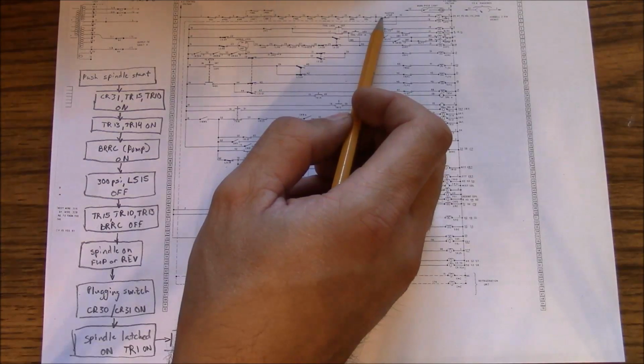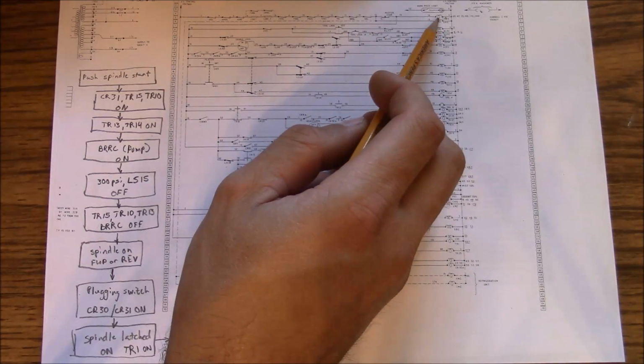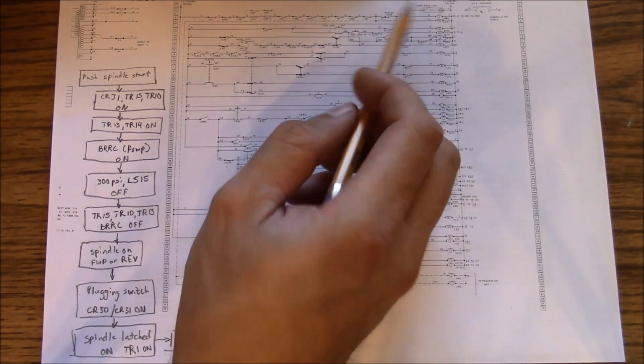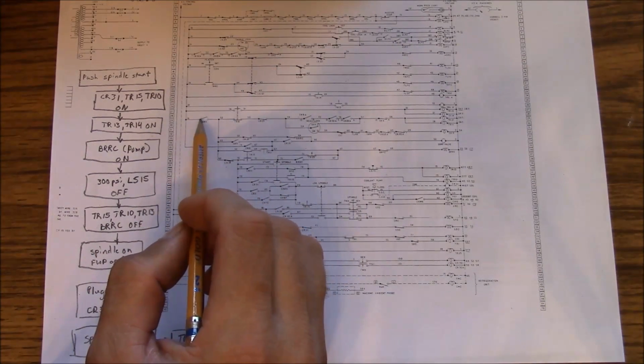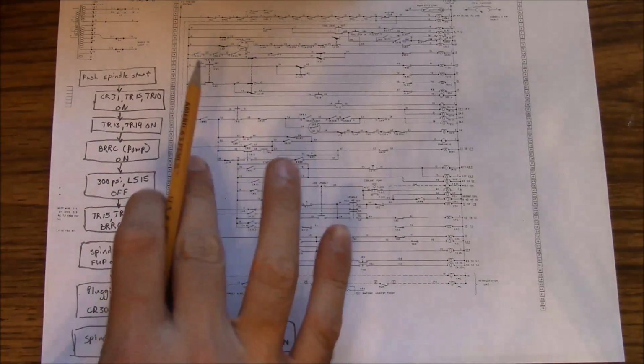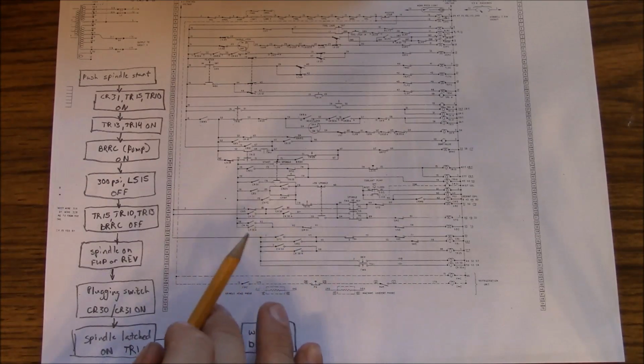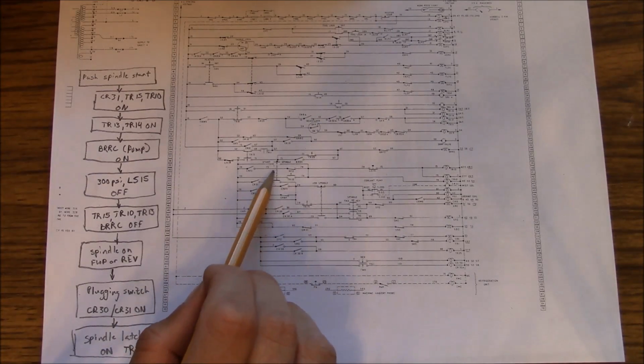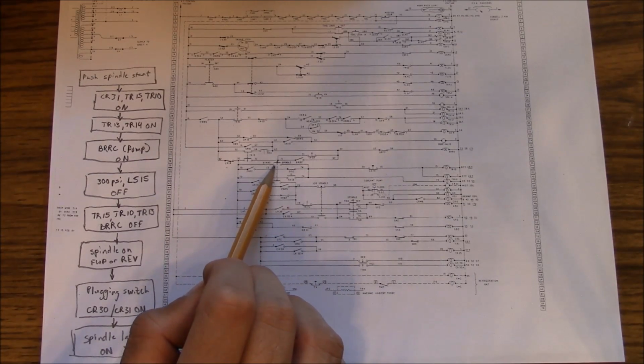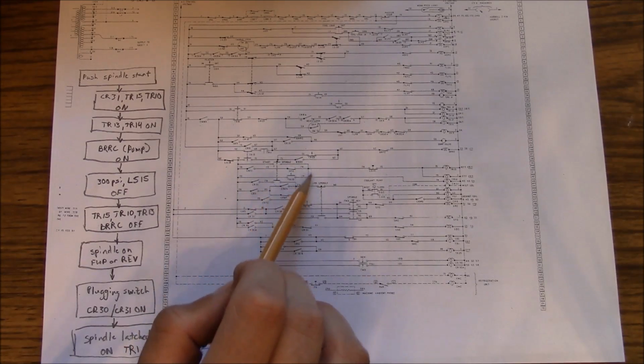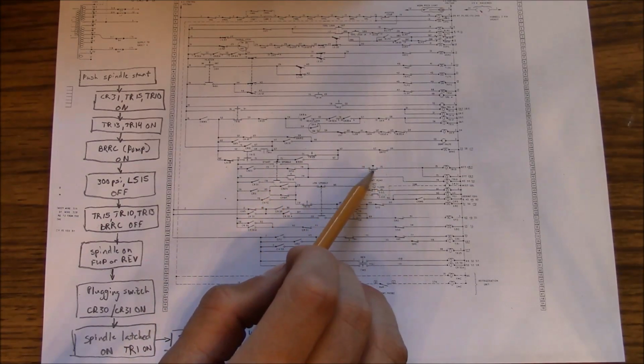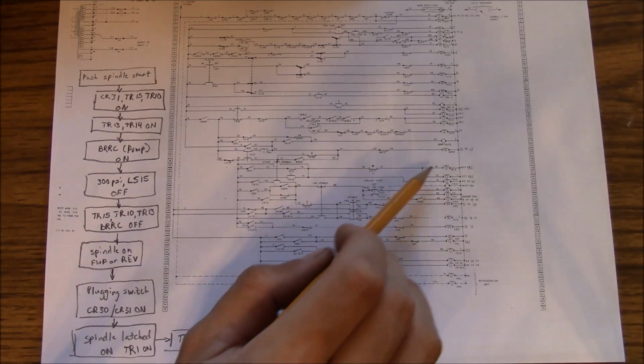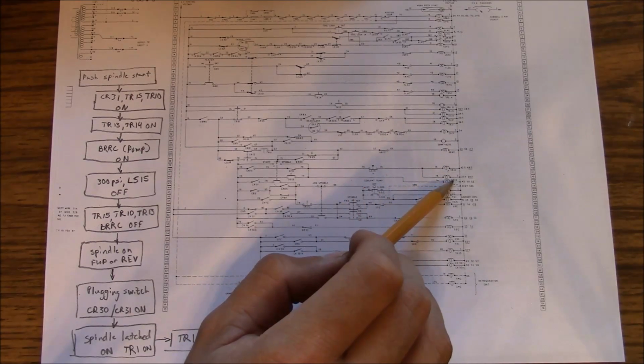So all these things have to be closed in order for CRMS coil to come in and basically close this switch and provide power here. So assuming that we're not in E-stop, here's what happens. So we push the spindle start button. It sends power over here through this limit switch here into TR15 and TR10.